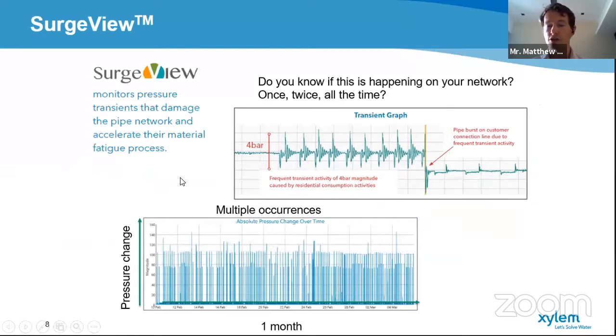The Surge View solution monitors the pressure transients that I referred to on the network. Frequent occurrences of these pressure transients or excessive magnitudes of transient can introduce fatigue to your pipes, which over time may reduce the asset lifetime. It's important to identify these early on so that you can address the operational factors that may be causing them and increase the lifetime of your assets.